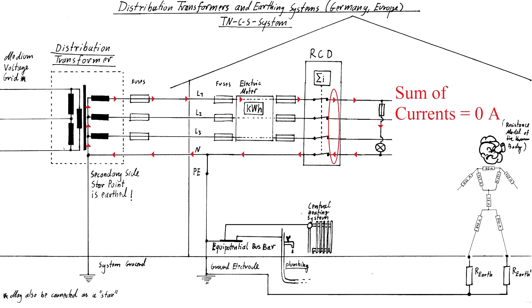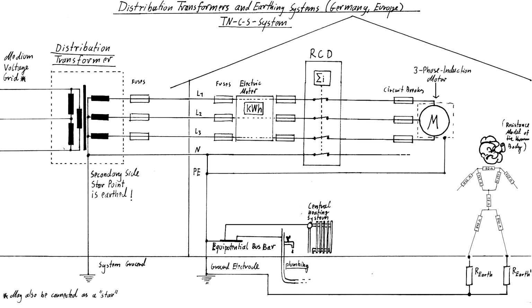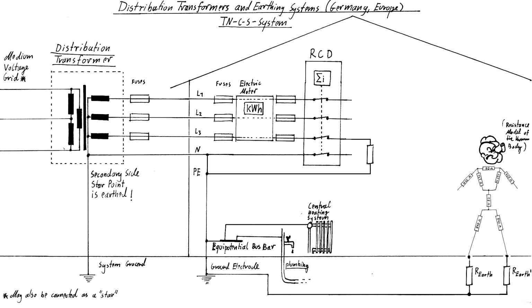Now a symmetrical three-phase load is connected. Again, all currents enter the load via the RCD and are returned through it again. The sum of the currents is again 0 amperes. But if we now connect a load between one of the phases and the protective earth, the current that returns to the distribution transformer does not pass through the RCD, but uses the PE as a return path. If the current sum is now higher than what the RCD is rated for, it will open all its switches and disconnect the load from the grid.